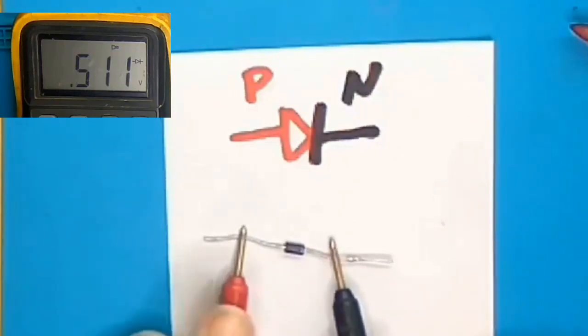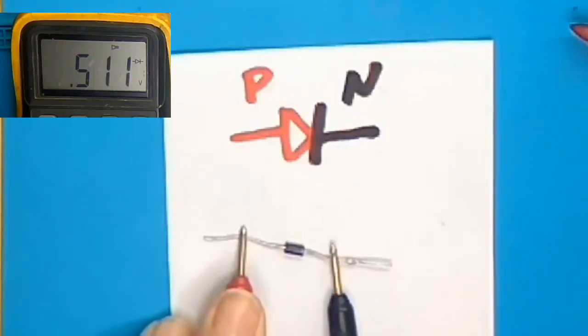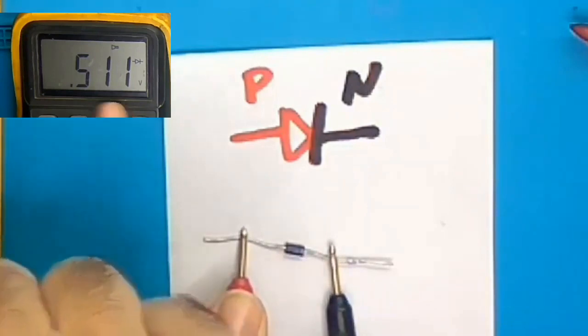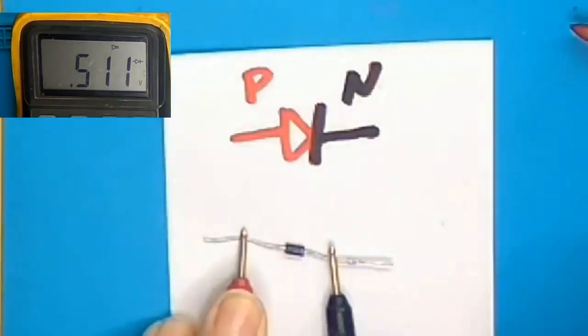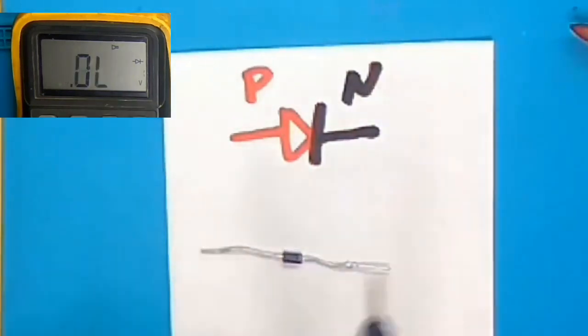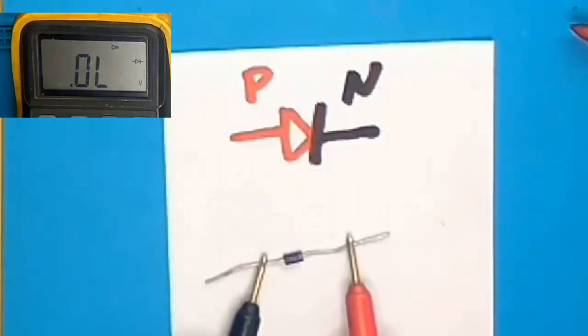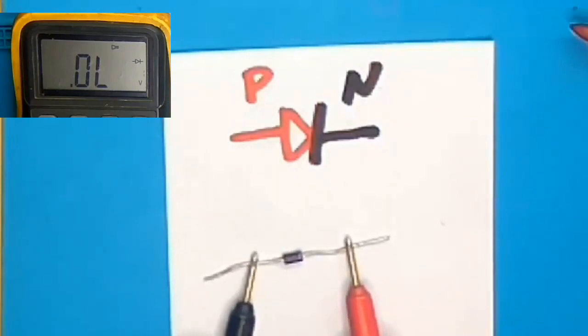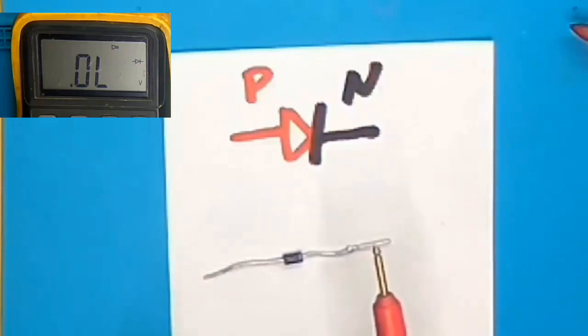We see here we've connected it correctly. It shows 0.51, 511, so it is 0.51 right here. We have a voltage drop, so it's right, from 300 to 600. It's okay. And backwards, it should show us nothing. You see here I've reversed it now. Reverse shows nothing, so it's correct. Similar readings should also be shown on the circuit.